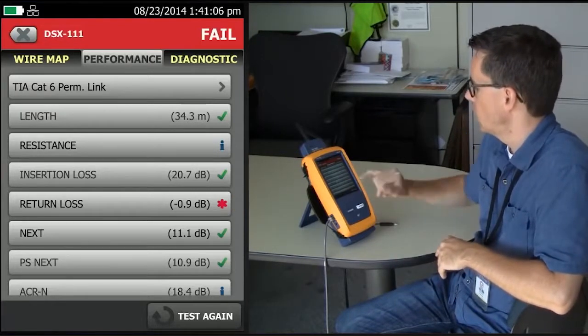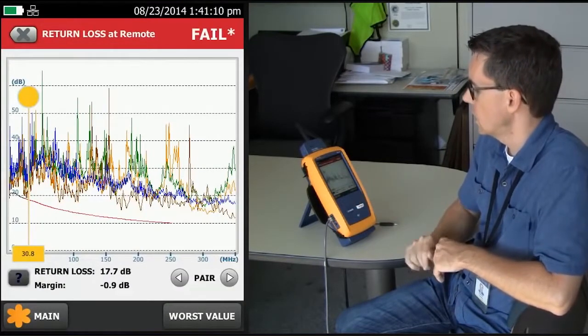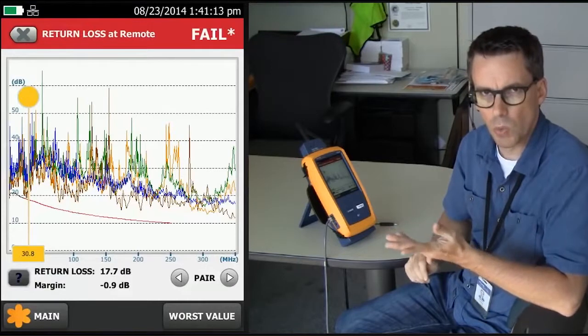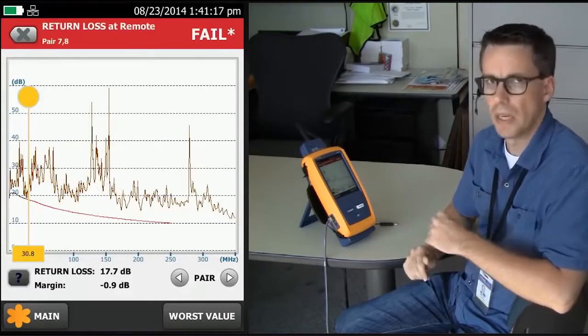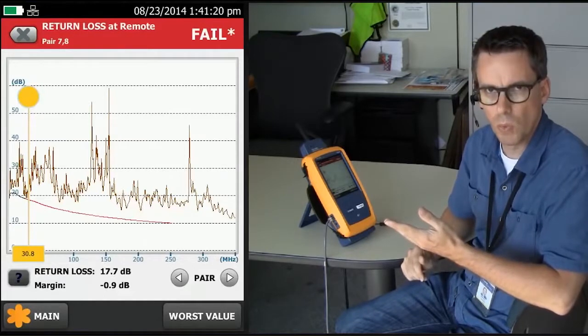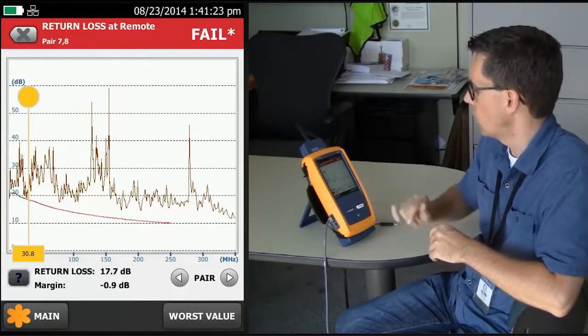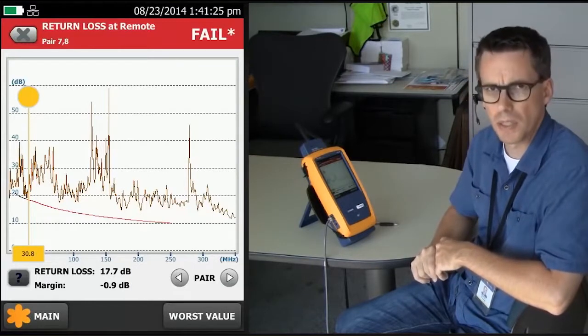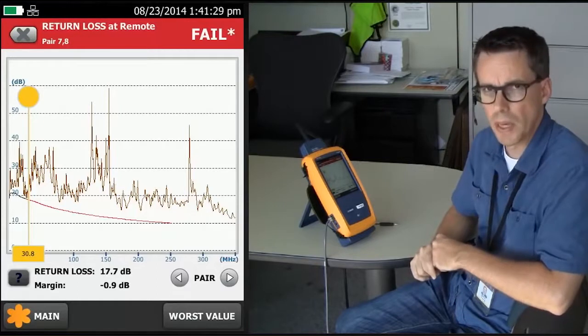If we tap on return loss, what we see here is all four pairs. And again, we want to see which is the worst performing pair. So if I tap here next to pair, it's going to automatically jump to the worst performing pair, the one that caused the fail, or actually the marginal fail of minus 0.9 dB. And in the top left-hand corner, it tells me it's pair 7.8.